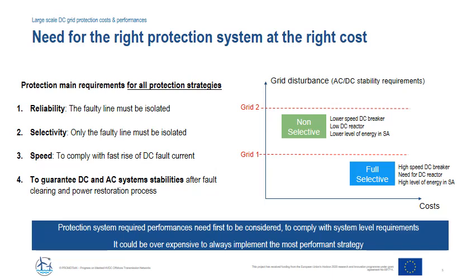If the AC system is operating close to its stability limits, it might not accept a large grid disturbance, as illustrated by grid 1 in the figure on the right. A fully selective fault clearing strategy would be certainly more adapted for protecting the DC grid in that case, but probably at a higher cost. However, if the grid disturbance requirement is lower, as illustrated by grid 2, it is expected that a slower and more cost-effective non-selective protection strategy will meet all the protection requirements. In other words, the question is, do we always need to be fast?